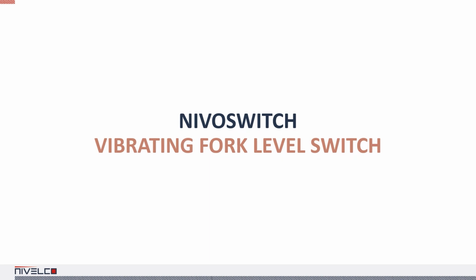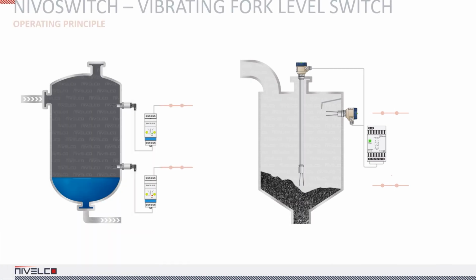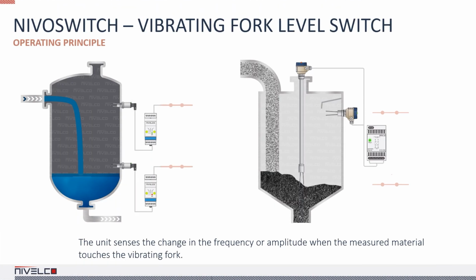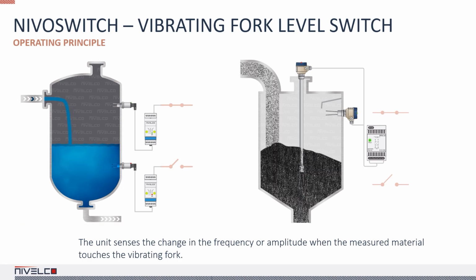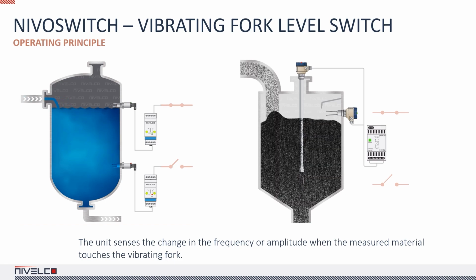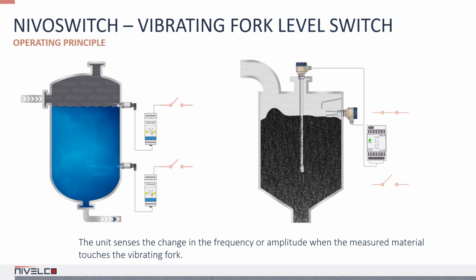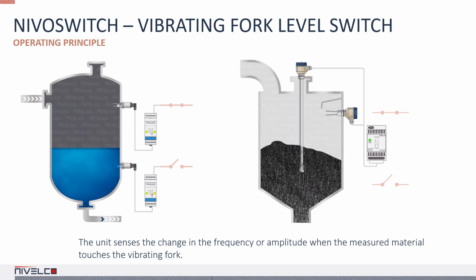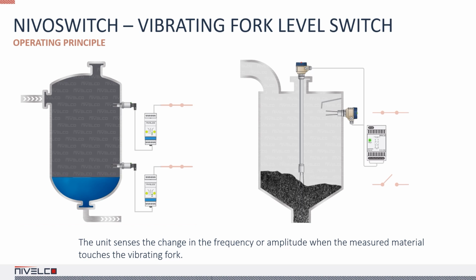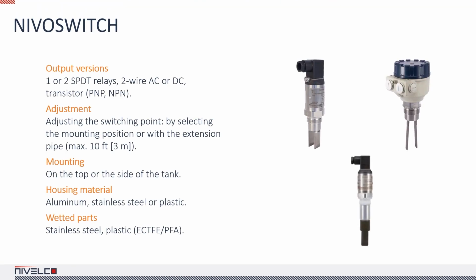NivoSwitch vibrating fork level switches are suitable for liquids, granular solids, and powders. The operating principle involves an electronic circuit that keeps a fork probe in an excited state by inducing vibration in it. When the medium touches the fork, the vibration changes or stops. As soon as the medium drops to a level where it no longer touches the fork, the probe starts to vibrate freely again. The unit senses the change in the vibration and sends out a signal after a pre-configured delay. The PNP-NPN transistor output versions can be connected directly to a PLC or a relay.